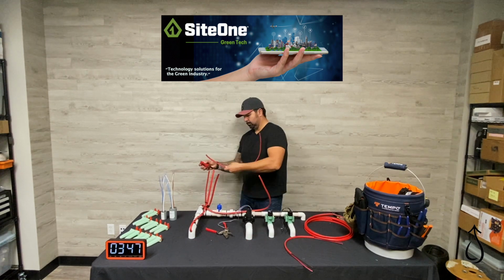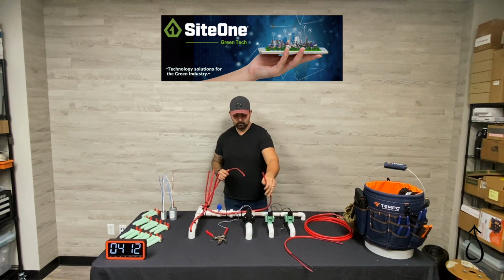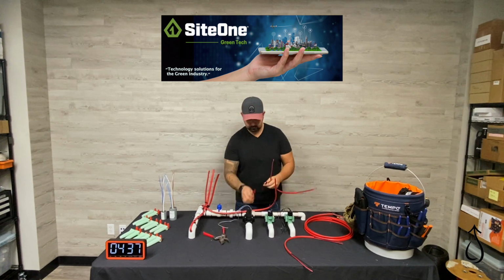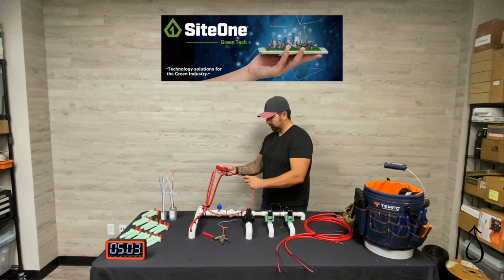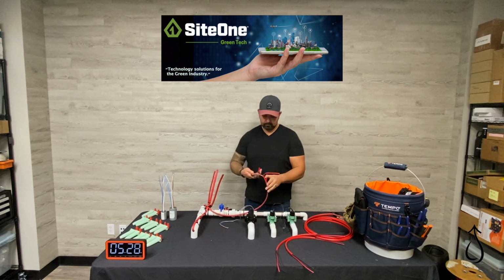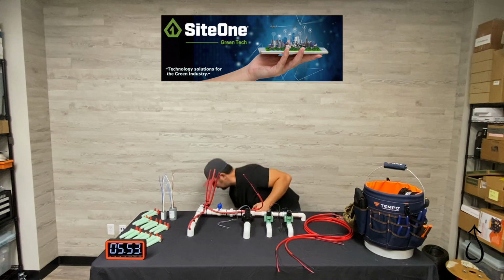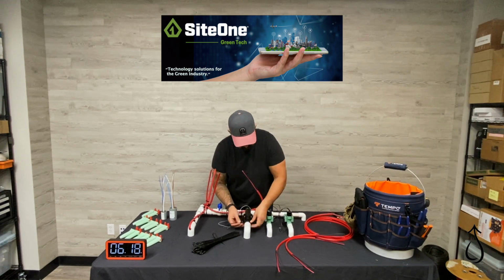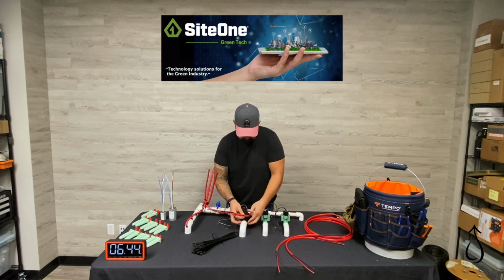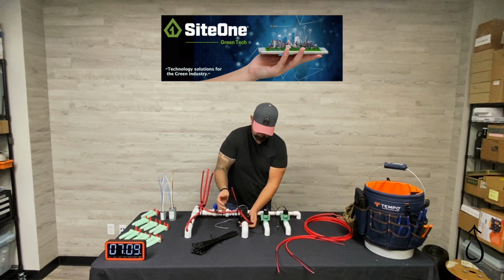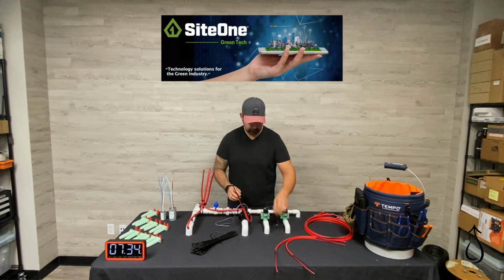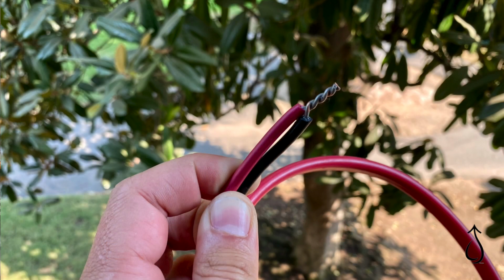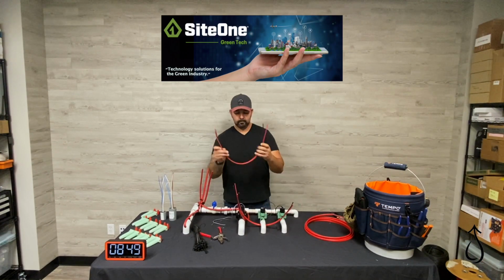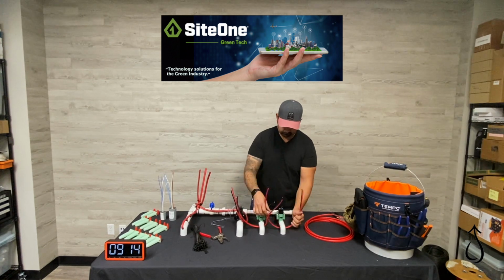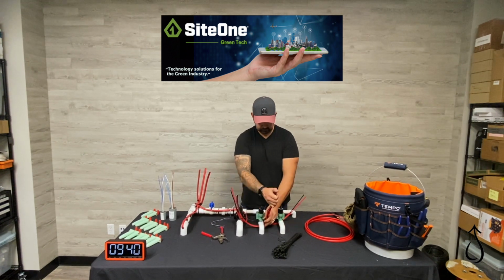I have heard of certain individuals claiming that the wire nut should make the wire splice. However, I have seen splices made with the wire nut where the splice was over tightened with cracked wires inside that wire nut. Using simple pliers can help you see and feel the correct amount of torque needed to twist the wires together without over tightening and accidentally cracking any wire in your splice. I prefer to see my wire splices, and I always prefer to use simple pliers to twist the wires together. Remember that the only true intention of the dry wire nut is to keep those splices dry. I like to install the dry wire nuts just finger tight.